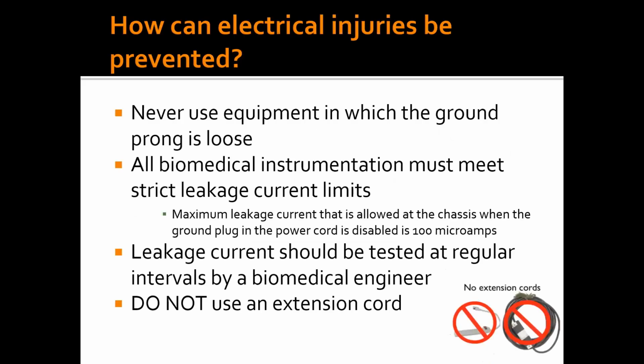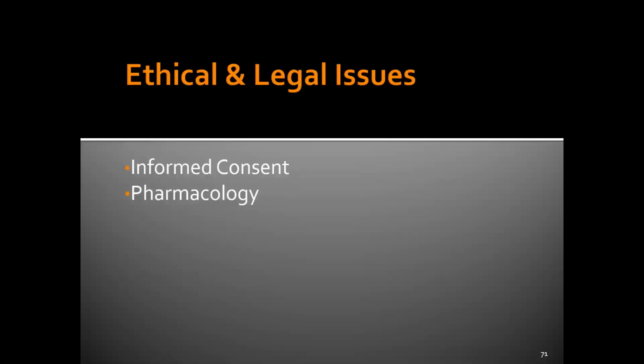Never use equipment where the ground prong is loose. Make sure that the instruments are routinely and regularly tested to meet the leakage current limits. Never use extension cords whenever possible, anything like that.